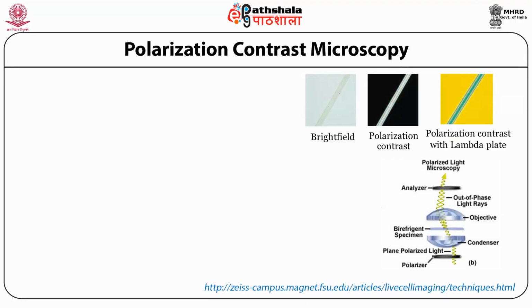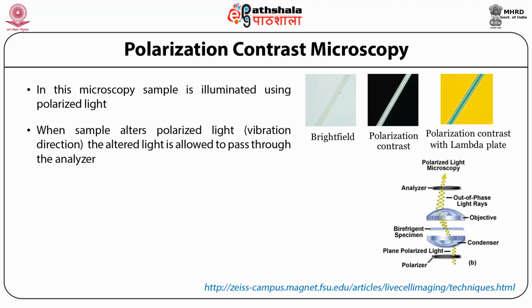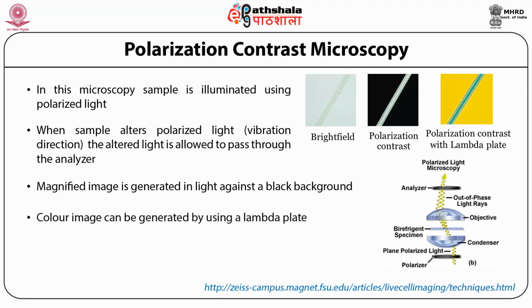Polarization microscopy. In polarization contrast microscopy, the sample is illuminated with polarized light, and the polarized light has a different vibration. So when the sample alters the polarized light, the altered light is allowed to pass through an analyzer, and that analyzer allows us to bring that polarized light back into the same vibration and same polarization, so that it can be visualized. In this case, the image is produced in a dark background, but by putting a polarization plate or a lambda plate, we can also invert the color and produce a colored image. This microscopy is used to visualize crystals as well as polymers.